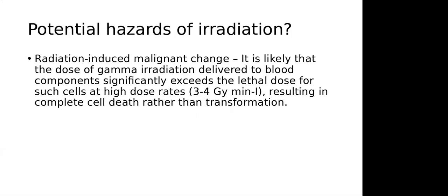Regarding potential hazards of irradiation: malignancy can occur if the dose of gamma rays is too low, as high doses cause complete cell death rather than transformation. The minimum dose is 25 Gray and the maximum is 50 Gray — irradiation should not exceed 50 Gray.